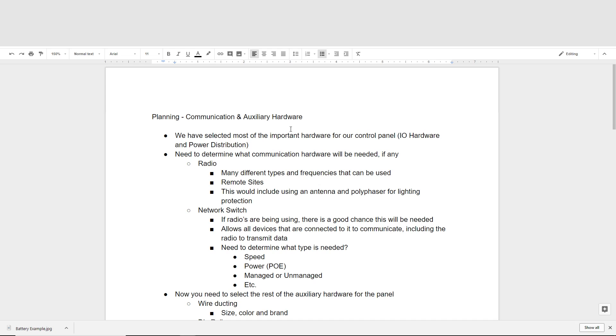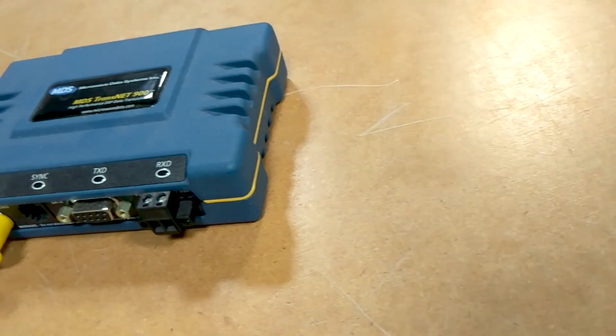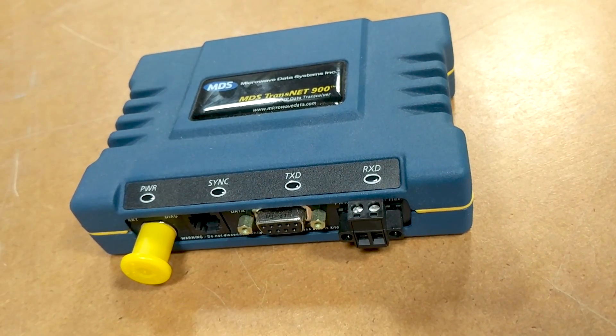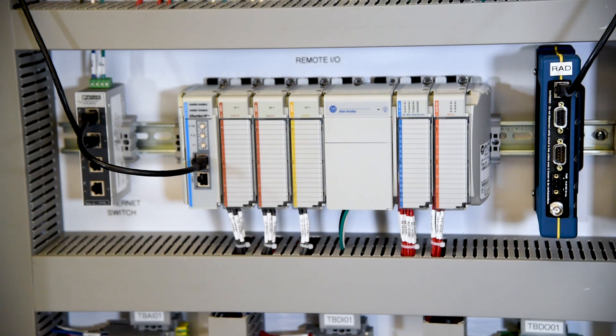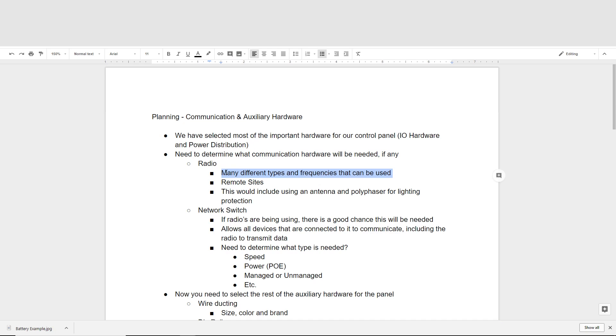The first thing we want to look at is any communication hardware that might be needed for this particular control panel — specifically, if we need a radio or not. In remote sites, we will very often use industrial Ethernet or other types of industrial radios to communicate to other locations. There are many different types of industrial radios that can be used in a lot of different frequencies and licensed frequencies depending on what the customer may want. With the use of a radio, we need to make sure that we use an antenna, some cabling, a polyphaser — which protects against lightning — and any other relevant hardware needed with the industrial radio.